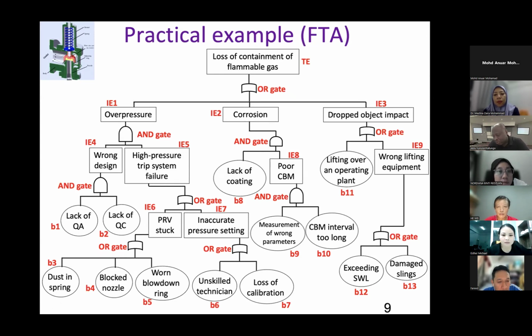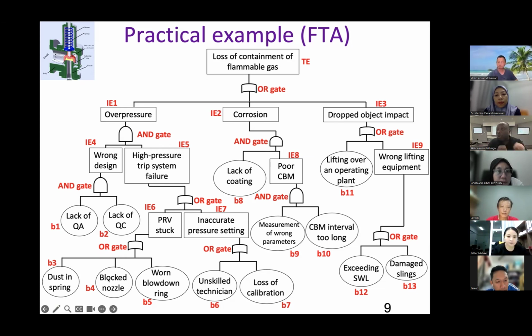Is that clear to everyone? Okay? If you have a question, please ask. And then you move on to the next intermediate event and develop it further. PRV is pressure relief valve stuck. It was stuck in a closed position and didn't allow pressure to go out. So that caused overpressure. And why is that happening? There was dust in the spring, which made it lose its compressibility. There was a blockage of the nozzle, which means excess air could not be released. Blowdown ring was stuck, okay? So that was not allowing the blowdown activity to happen.